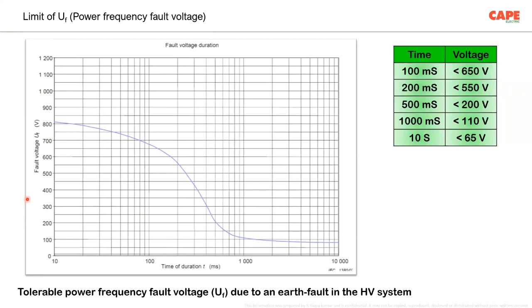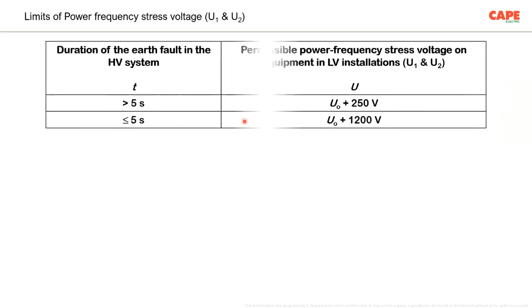IS 732, which is the code of practice of electrical wiring, as well as the upcoming National Electrical Code, has included this particular graph. Please note that this graph is from the IEC standard on basic safety measure, shock protection standards. So we are not going to include any new thing. It is adopted internationally. Every electrical installation must ensure that the shock voltage is made less than this.